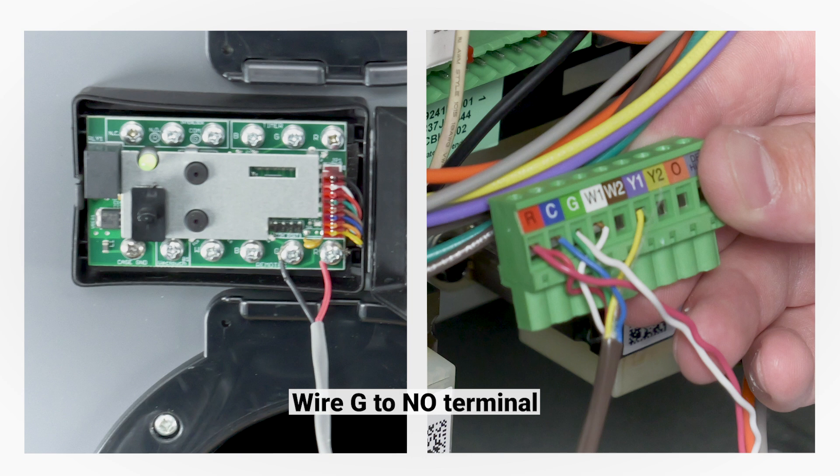Wire the G on the furnace or air handler to the NO terminal on the ventilator. Wire the R terminal on the furnace or air handler to the COM terminal on the ventilator.